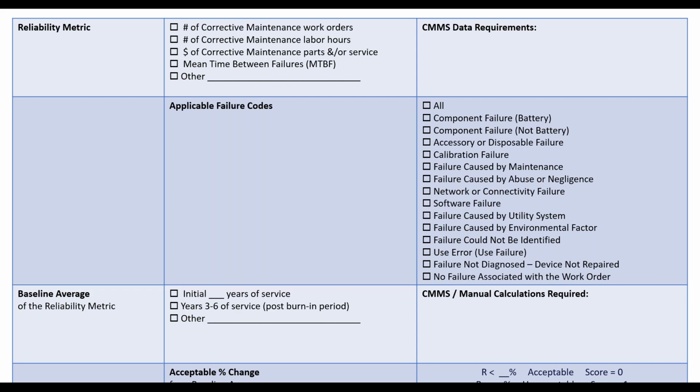You know, there might be 10 of the same make and model, there might be 500 of the same make and model, right? So you look it up once, you score it once and copy paste. What we do then, once we have scored, and I prefer to score every asset, because then we have that granular detail, and then we can zoom out. And we can say, let's look at our CTs, but let's look at them individually, right? And so we pull them out, we can see all 20 of them, and we start making overarching assessments.